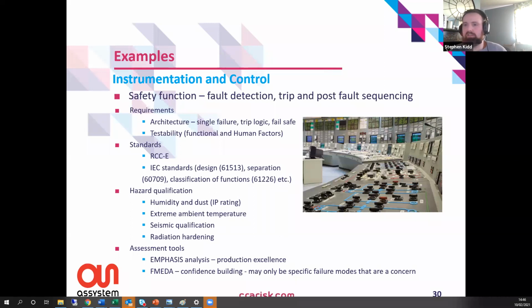With hazard qualification, again, we might need IP ratings, like for humidity or dust ingress. We want to prevent things getting into the cabinets and affecting the performance of the equipment. Extreme ambient temperatures, again, seismic qualification, or radiation hardening. If we're looking at sensors, for example flux sensors that are operating in the core environment, then we need to demonstrate that those are capable of functioning in extended exposure to radiation. And there may be specific tools to enable us to do this.